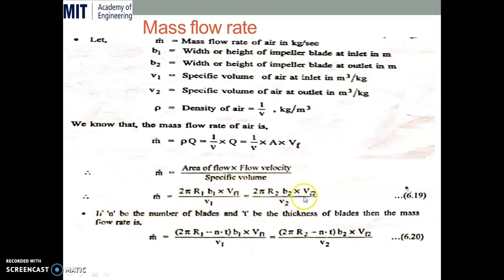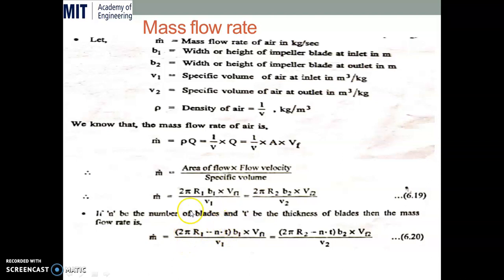Without considering blade thickness, that formula applies directly. If we account for n blades each of thickness T, we reduce the circumferential area accordingly. So we write: (2πR1 − n·T)·B1·Vf1 / v1 = (2πR2 − n·T)·B2·Vf2 / v2. This is the same concept used for guide vanes in a centrifugal pump. This gives the complete mass flow rate equation.